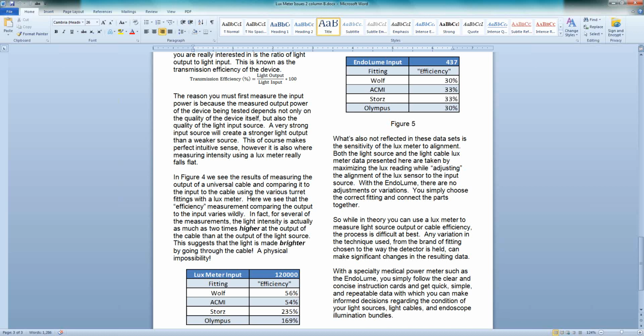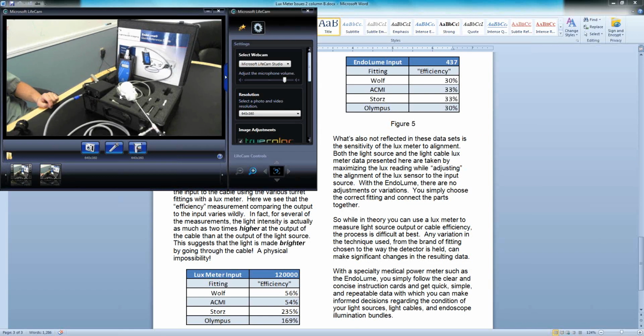So with a lux meter, the difference in trying to measure the output of these different turret settings, let me put this image and see if I can do this here a little bit. Make this image a little smaller, perhaps. So we can see that the light source here, I don't have one with a turret on it, but I have one where you simply change the nose piece settings. So right now, we kind of see how bright this light is when it's set up for a Storz light source. If I were to remove this adapter, it is now set up for an ACMI light source. It's a little hard to see on the camera, but we'll see there's a lot more light. It's a lot brighter image out of it. This is exactly what this paper talks about.